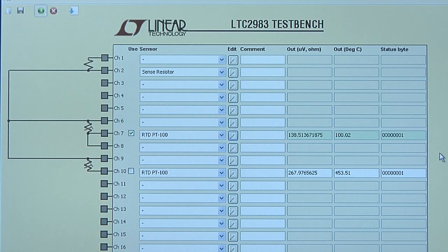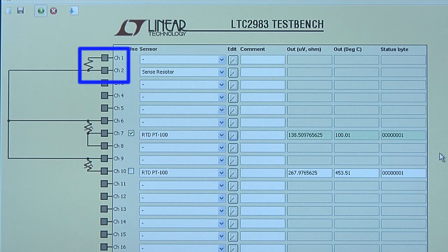As you can see, the demonstration system is collecting the LTC2983 output, which is precisely reading 100 degrees C. The corresponding R-sense resistor is tied between channel 1 and 2, and its value is stored in the LTC2983. The 2K ohm sensor resistor is shared between all three sensors on the demonstration board.